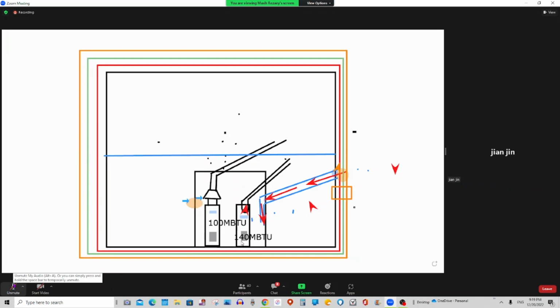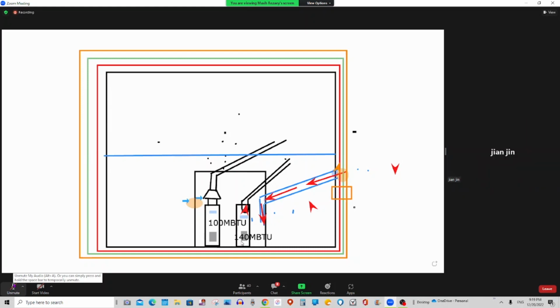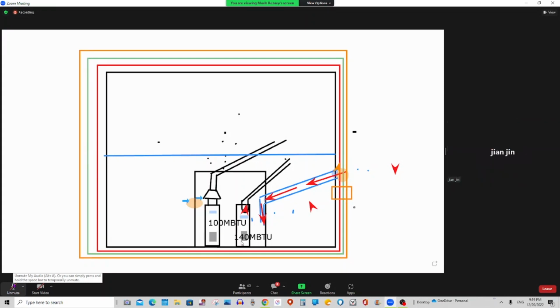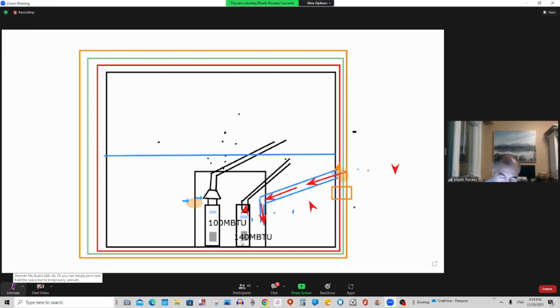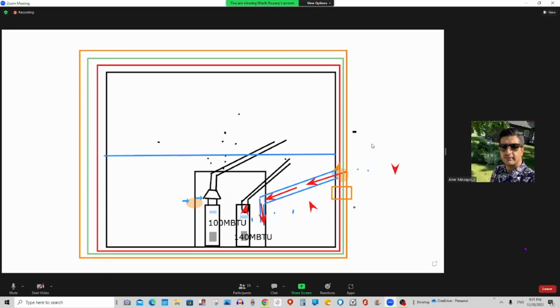Okay, sir. May I have one last question? Yes, sir, go ahead, please. As you said, if we compare the two tables and the natural draft one is bigger than the total one, do we choose the bigger one? Yes, we choose the bigger one. Tomorrow night, I will give you another question in which the natural draft is the bigger one, and we can discuss. Read 8.1, 8.2, 8.3 and 8.4. Read the clause numbers slowly and understand. When you read it properly, you will understand and it will be very easy. Otherwise, it's going to be hard.